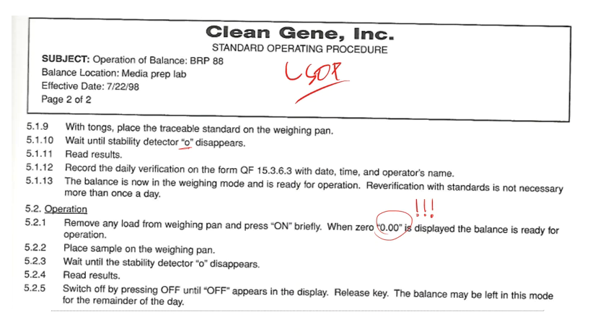Then it says record the daily verification on form QF 15.3.6.3 with your date, time, and your name. So this is basically the company's way of saying, yeah, we're going to do this every day. So we're going to have a calibration weight that is going to be dedicated, and we're going to take that weight, put it onto the balance every morning, and double check to make sure that balance is providing a proper number like it should be day after day after day. Because like with everything, as you use it, these things can mess up if you're not careful.